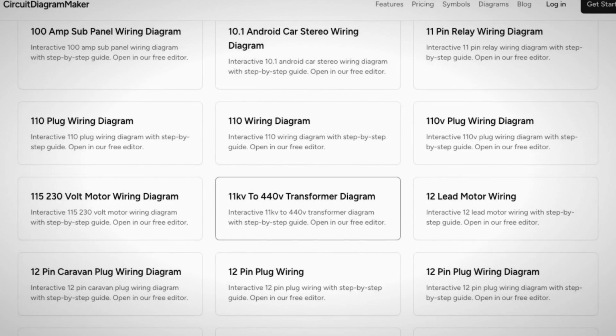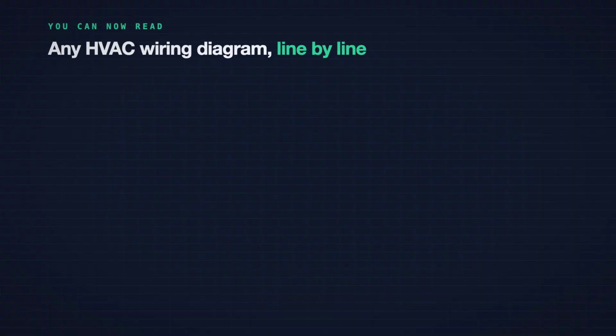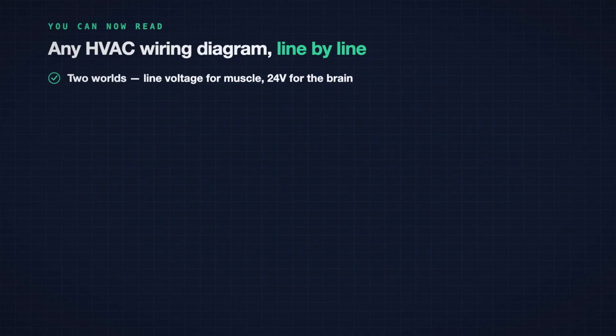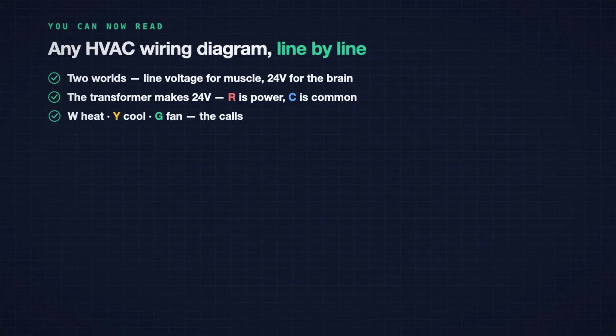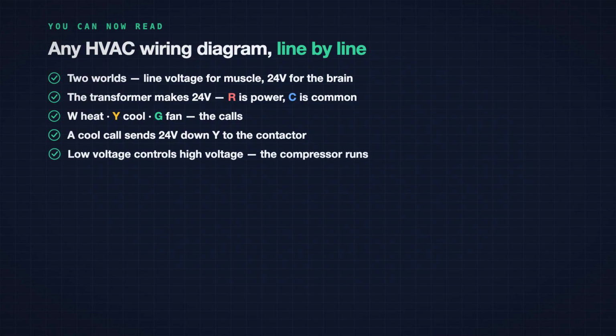So here is the whole diagram, one more time. 2 worlds, line voltage for the muscle, 24 volts for the brain. A transformer bridges them. R is power. C is the common return. W, Y, and G are the calls. Heat, cool, fan. A cooling call sends 24 volts down the Y wire to the contactor. And the contactor, a heavy relay, hands the compressor its 240 volts. Low voltage controls high voltage.